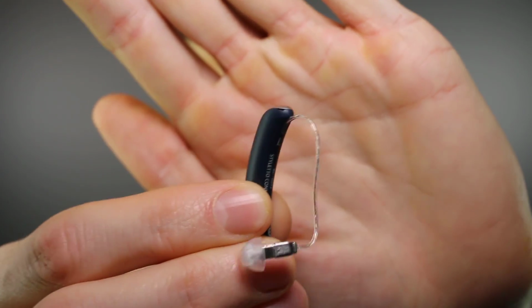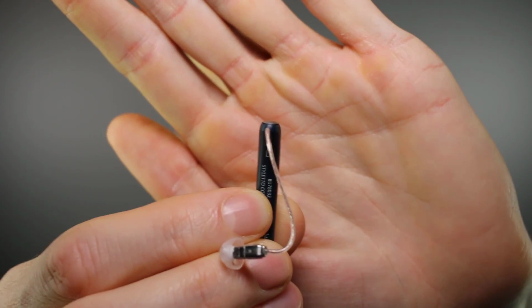The second thing that bugs me about these hearing aids is that they have a fixed receiver wire. What I mean by that is the wire that's coming off of this hearing aid cannot be changed in clinic. It is fixed inside of the unit. That means that if you have any issues with the receiver wires, these hearing aids are going to have to go back to the manufacturer to be repaired. It's not something that can be done in your local audiology clinic. So instead of it being a really quick change inside of your local clinic, it is going to end up being a really long change because you have to send this all the way back to the manufacturer, get it back, and get it back on your ears.